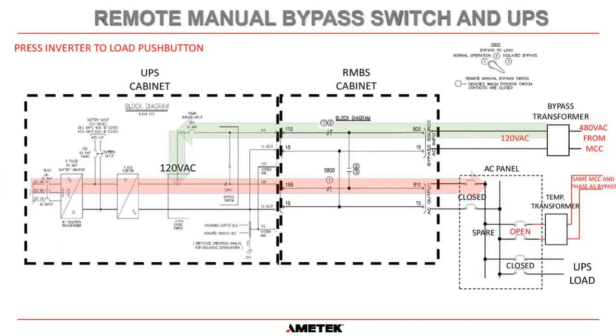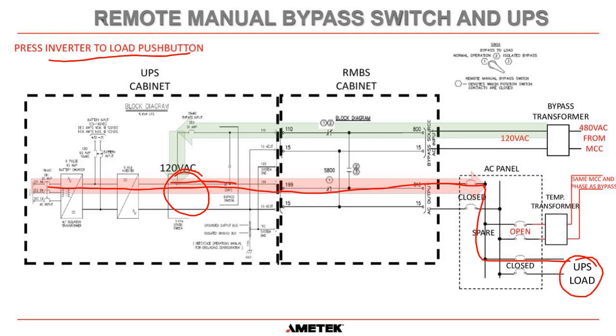And then the last thing we do is we press the inverter to load push button on the UPS, which will tell this static switch here to turn on. And therefore, we're going to supply power as we should be through the UPS, through the RMBs, through the AC panel, that closed main input breaker, out to our UPS loads here. So now we are back in complete battery backed up normal operation. And we've done this without losing power to the UPS critical loads. And you now have an external RMBs that will allow you to go in and do maintenance on this UPS cabinet whenever you need to do so. And you can lock out, tag out all of the power supplies, and you can work on it safely.